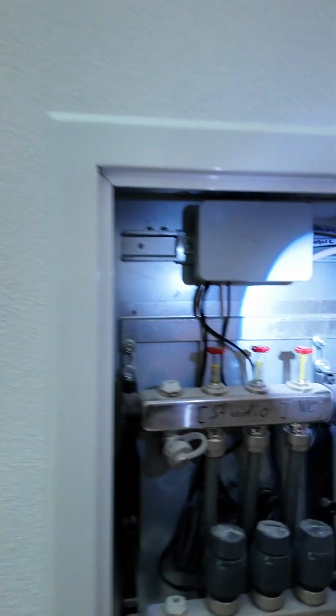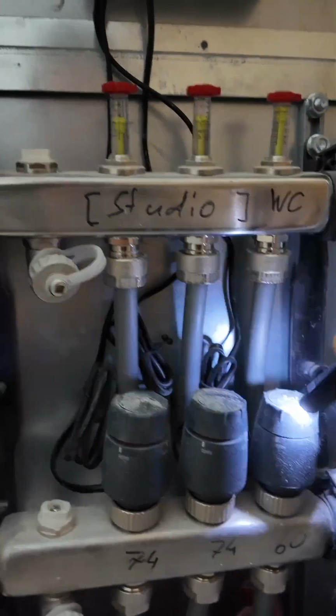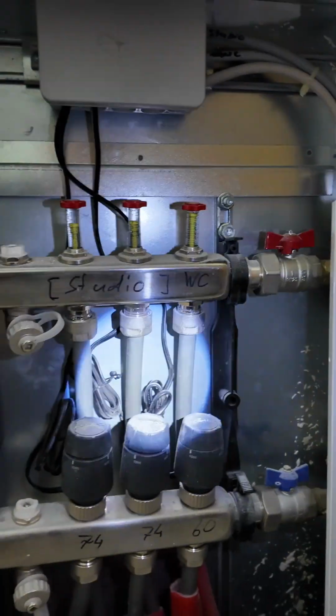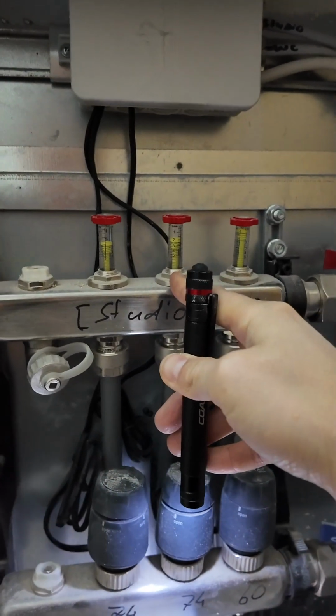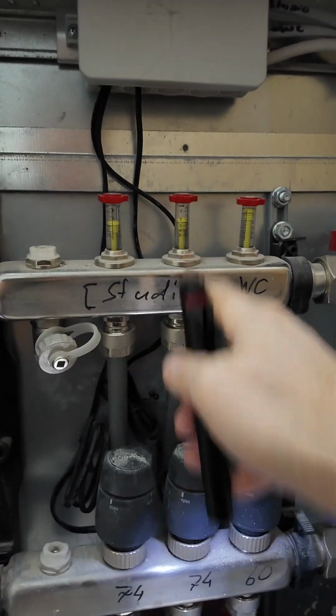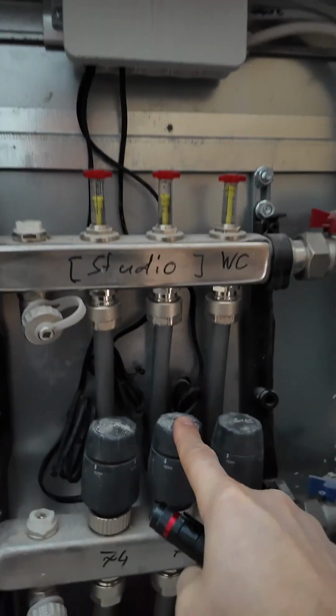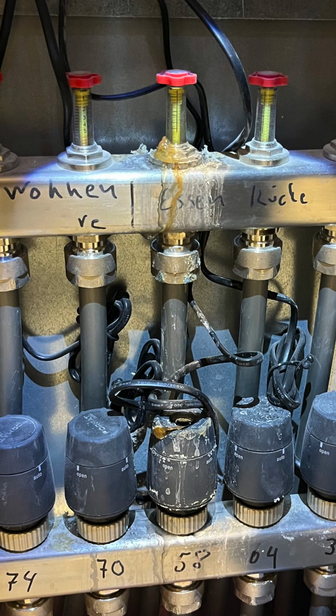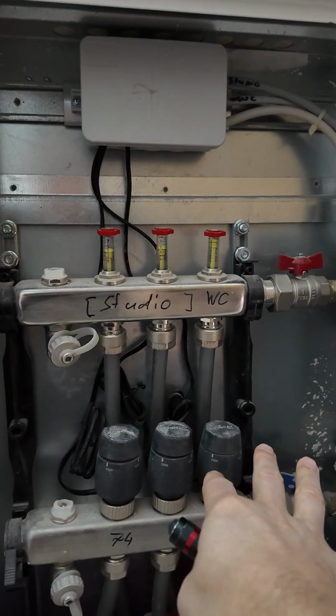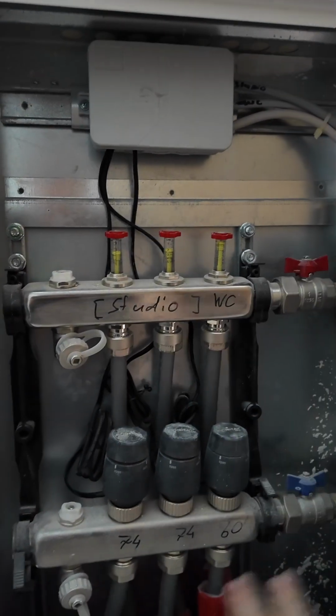You have to consider all those factors, and our heating system was not working for a while. And it took us a while to realize why. In fact, the reason was because all of these valves here, you can see here, they're connected electrically and we had a leak here. So one of these was leaking water from the Heizwasser, or the heating water, directly down, drip, drip, drip, onto the top of the valve, shorted the valve out, which tripped the breaker switch, and therefore none of the valves got any electricity at all. And therefore, there was no flow at all through any of the floor heating of the whole house. So just another thing to consider, if your heating stops working, check your breaker switches, check also the pressure.